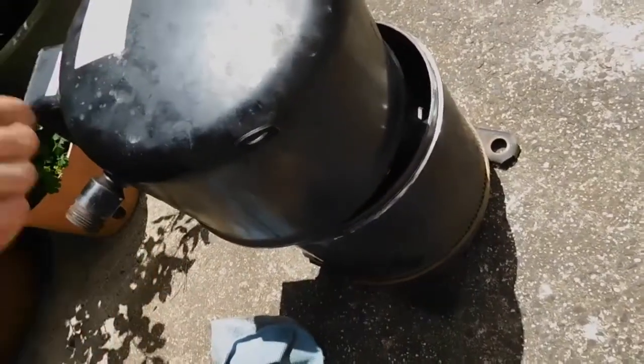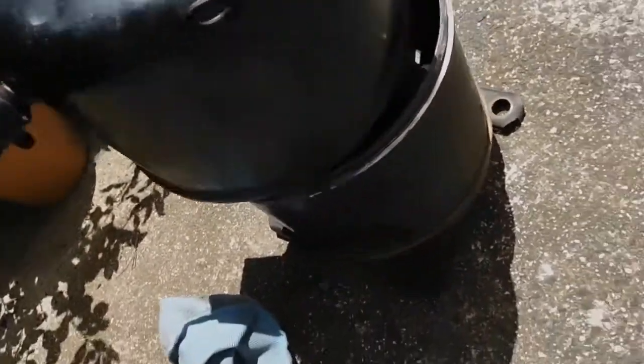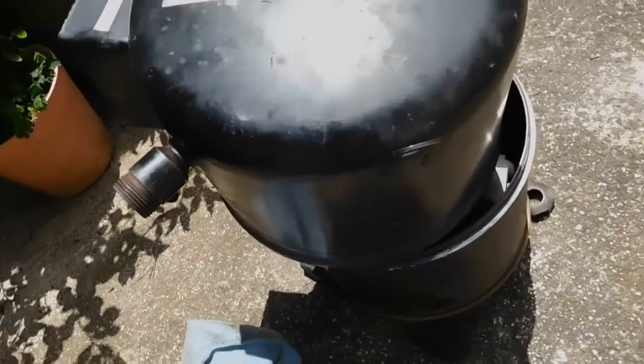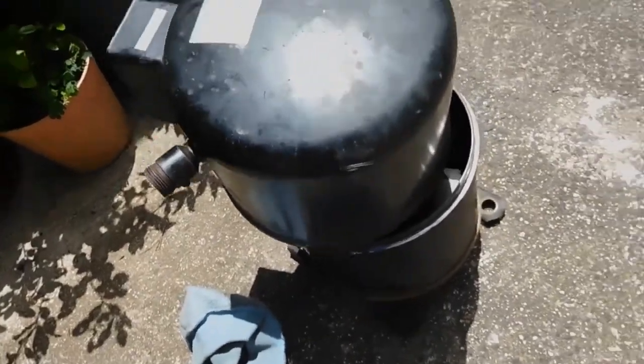Just my luck — there's no way it actually attaches to the bottom of this casing. Because on the Maneurop big MTZs, the top will just pop off once you cut through it. You cut through that thickness there so you don't contaminate the insides, and then the top normally just pulls straight off. But here it's a whole different kettle of fish. Maybe more grinding work involved.